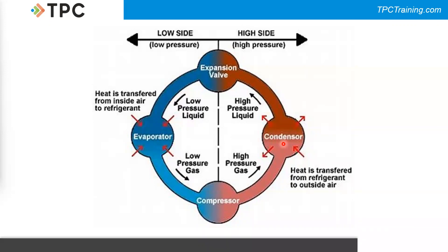Once we have it as a high-pressure liquid, we want to use that liquid over again. We do that with the expansion valve. The expansion valve restricts the flow of that liquid. Imagine a balloon: you blow it up, then start letting air out — the higher pressure inside pushes out and equalizes. That's what happens in the expansion valve: we slow down the liquid going through and open it up to a larger opening, reducing the pressure. So our four major components are the evaporator, the compressor, the condenser, and the expansion valve — each with a unique role.